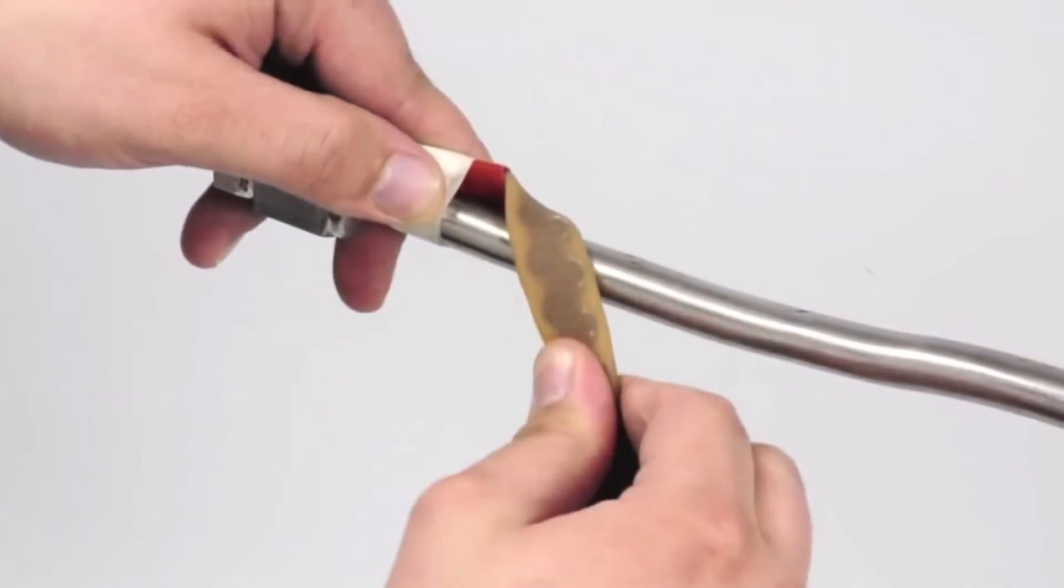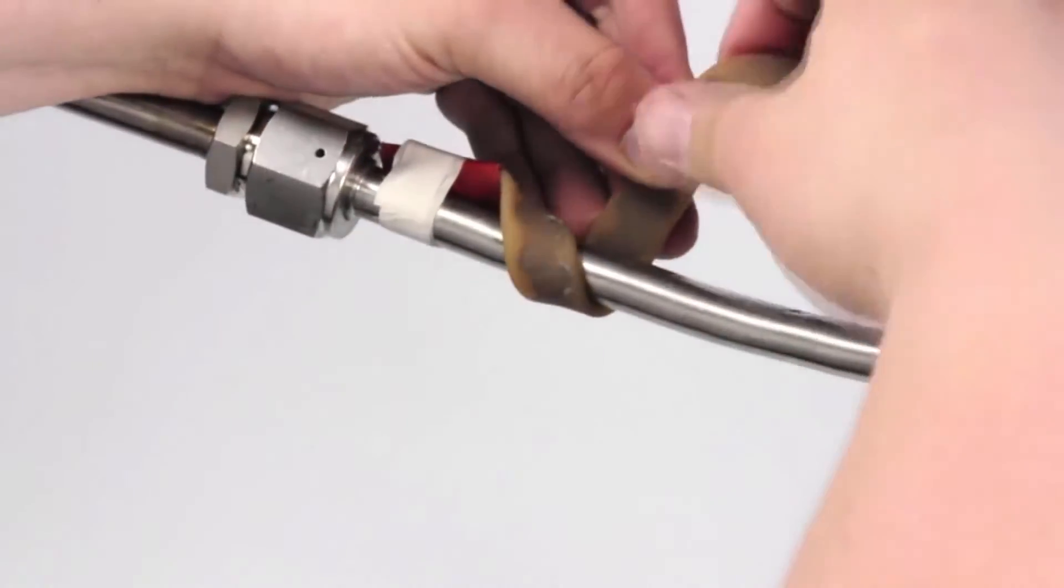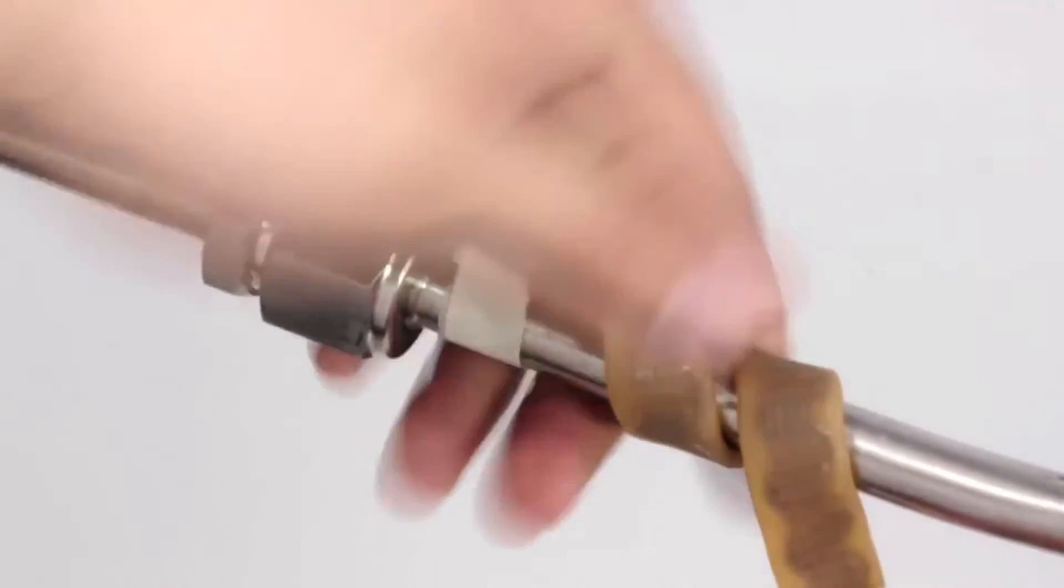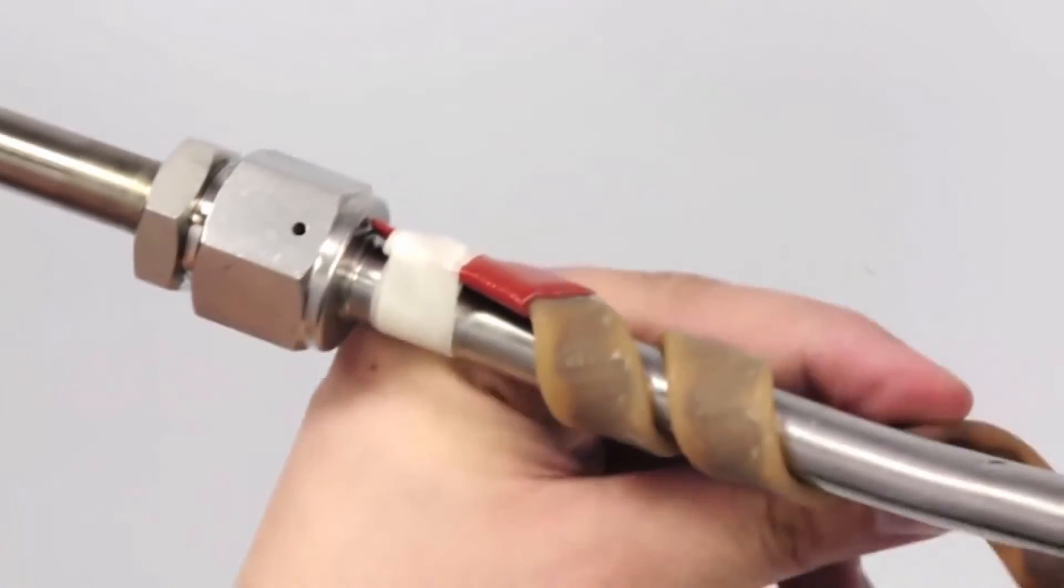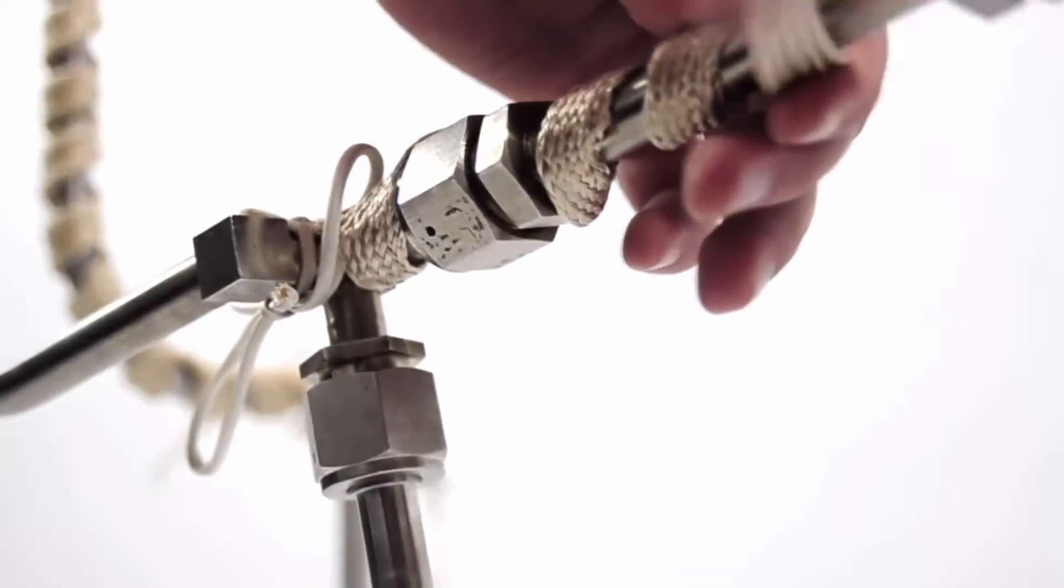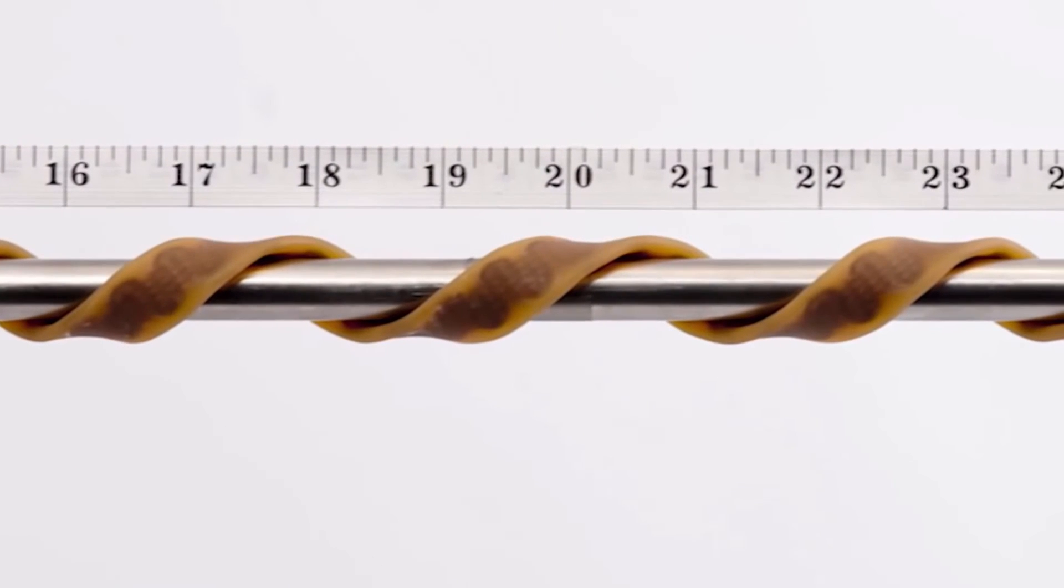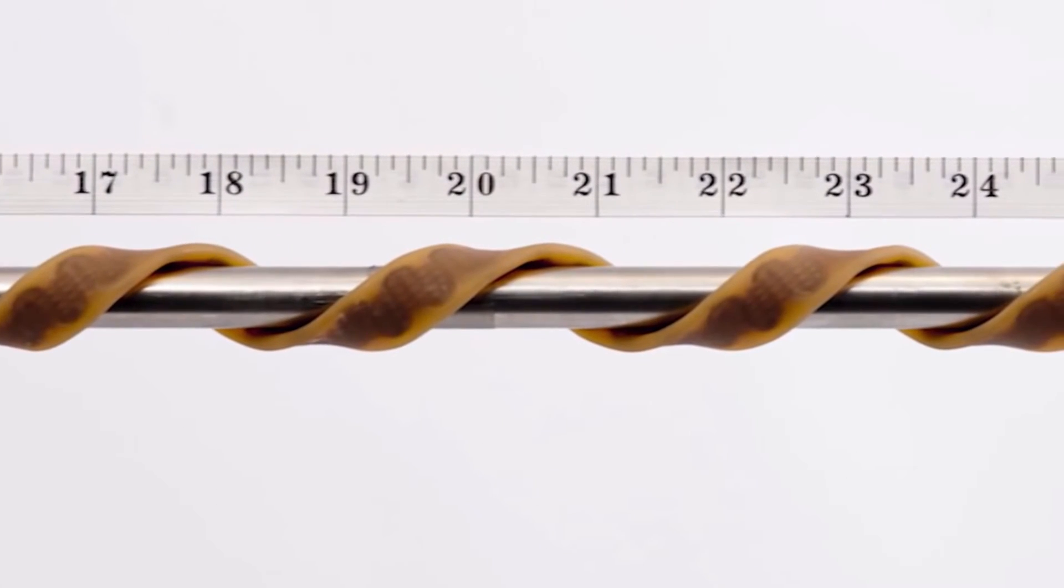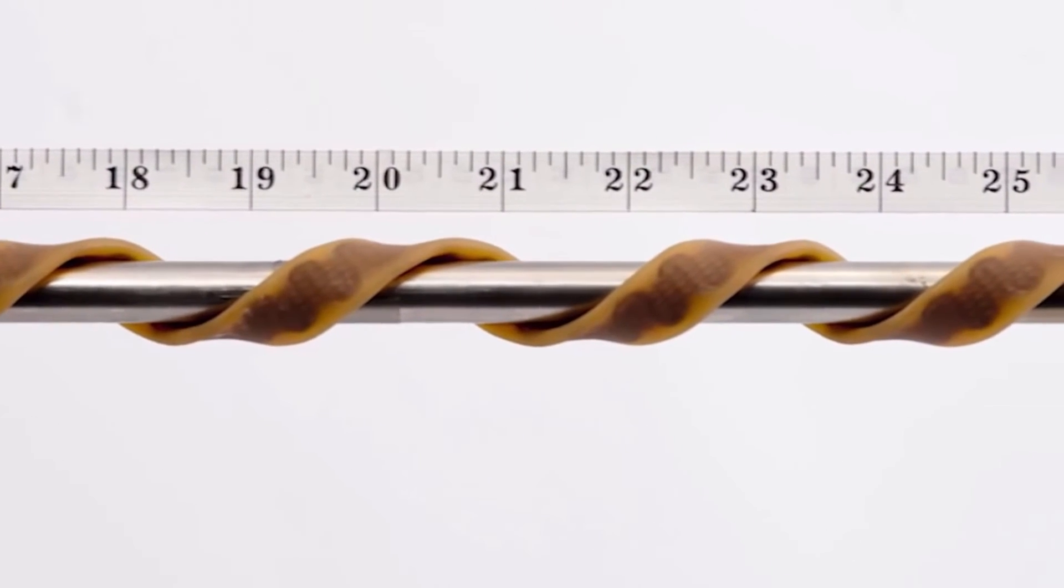Spiral wrap the heating tape onto the surface that will be heated. Make sure the length of one entire side of the heating tape is in full contact with the surface. The distance between spiral wraps is dependent on the uniformity requirements and the amount of available heating tape.